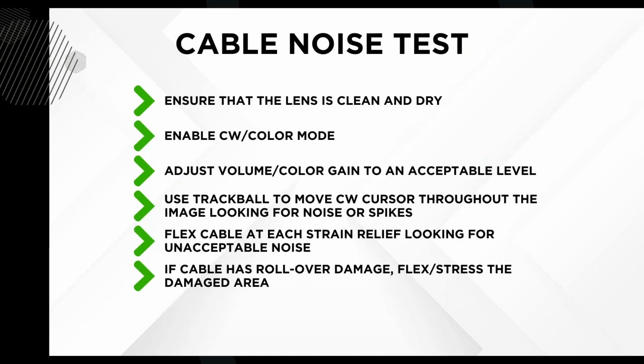One of the things I would do when I come to the cable is run my fingers or hands through it, to see if there are any flat spots, if it's been run over by a tire or a wheel of the ultrasound system. If there is, then I would check that area. I'll show you what it looks like on the system here.